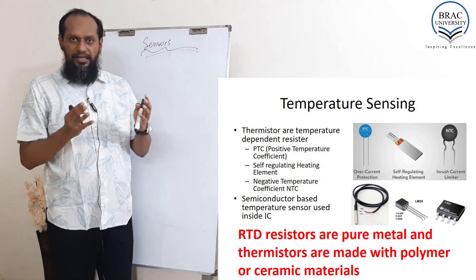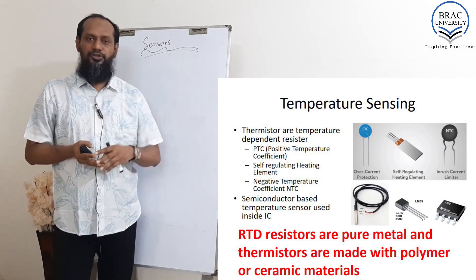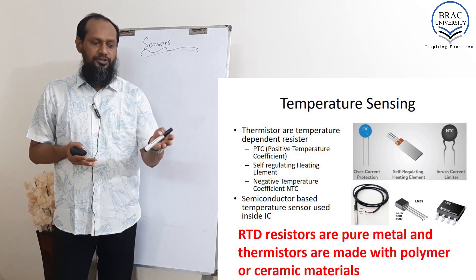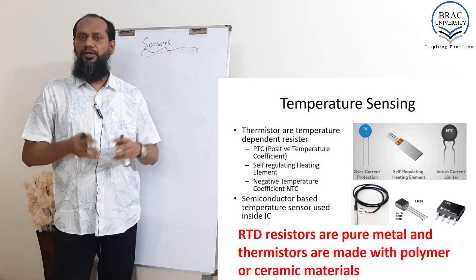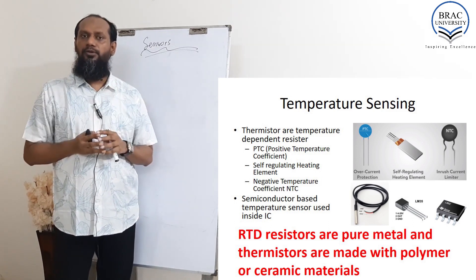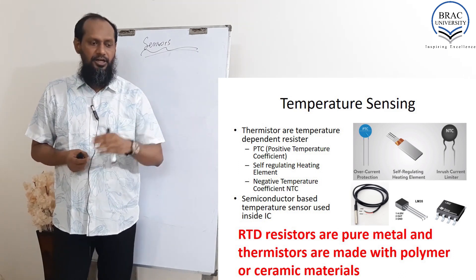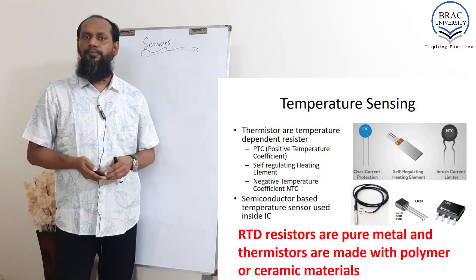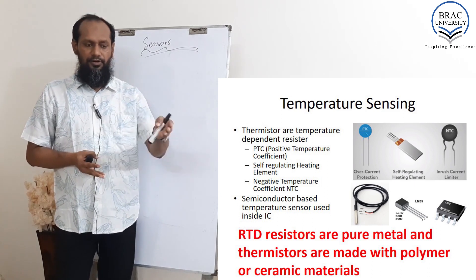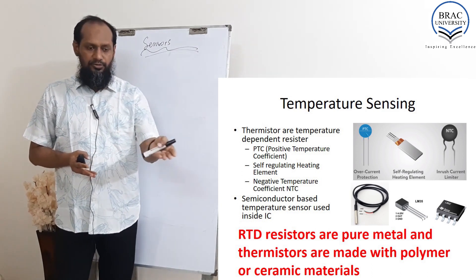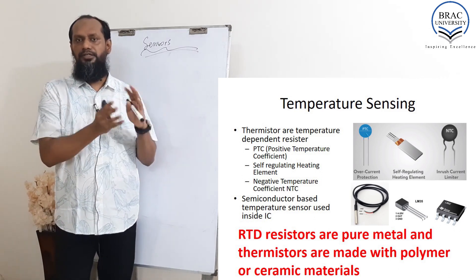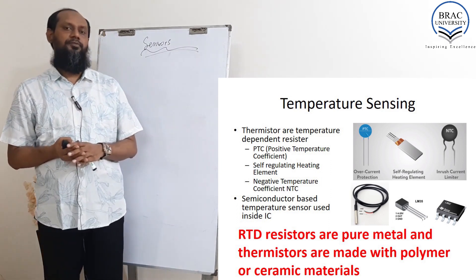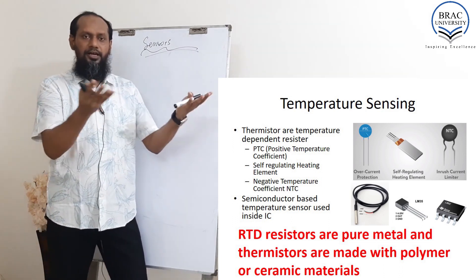Some people can get confused with RTD and thermistor. The small difference is: RTD resistors are pure metal, while thermistors are made with polymer or ceramic materials — that is the materialistic difference. RTD uses platinum, copper, nickel, or nickel-iron for sensing temperature, and for thermistors we use polymer and ceramic material. The main difference is the material used.